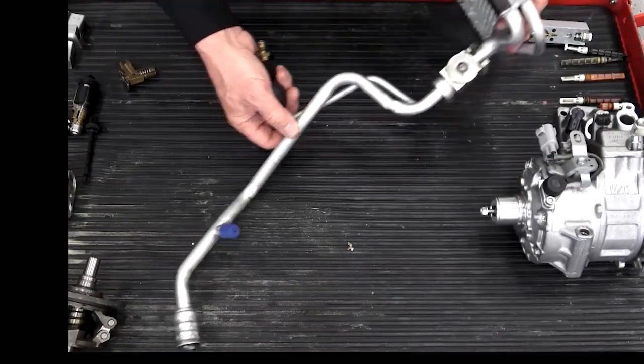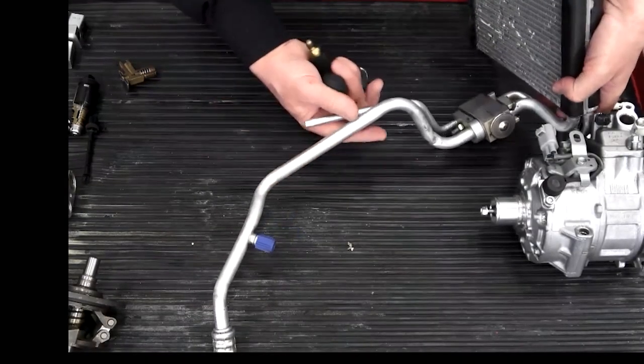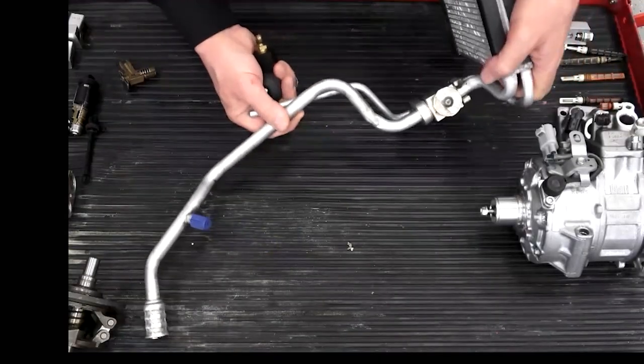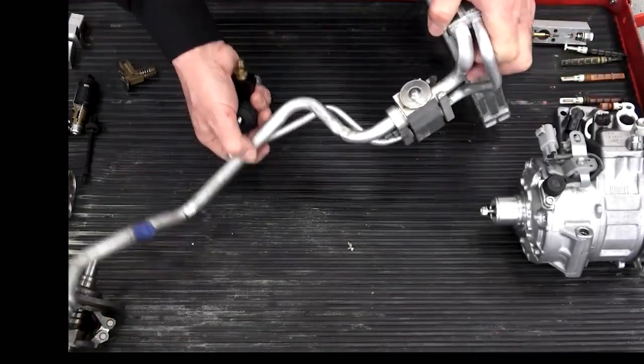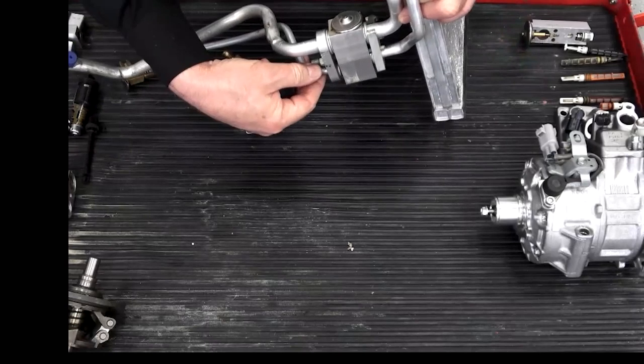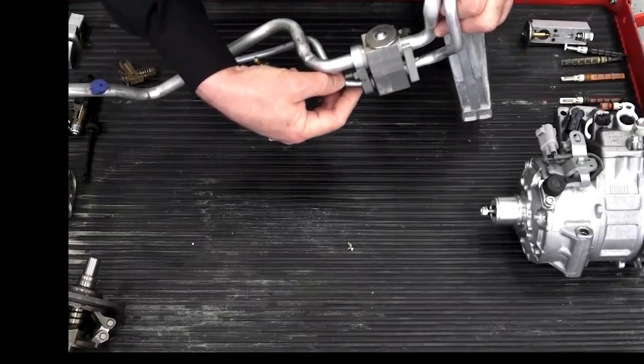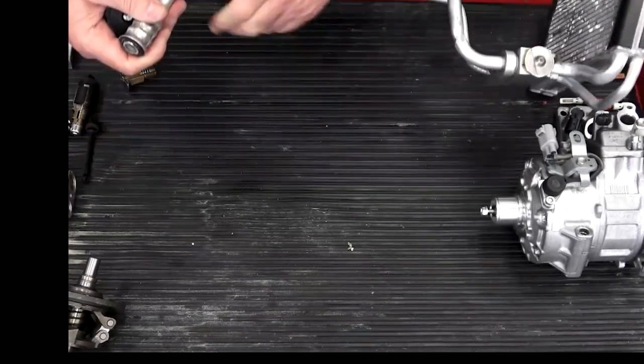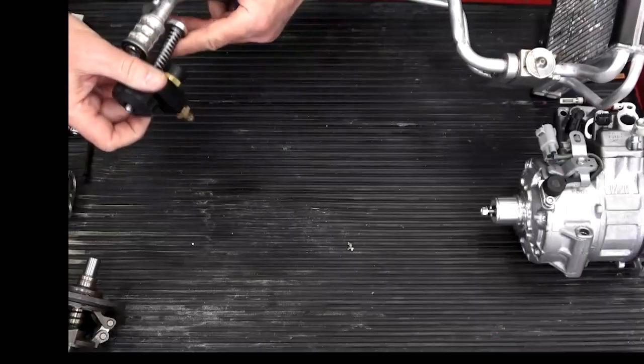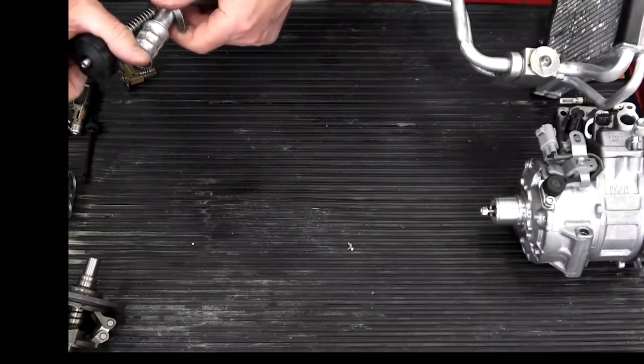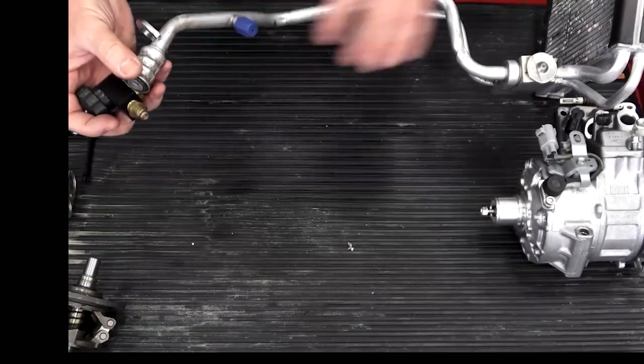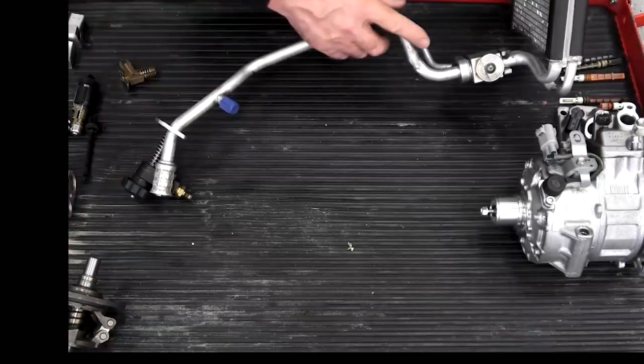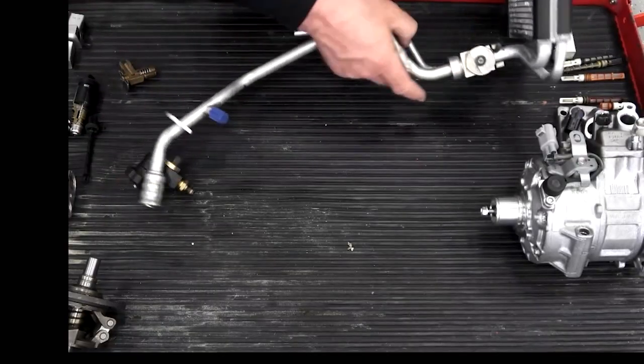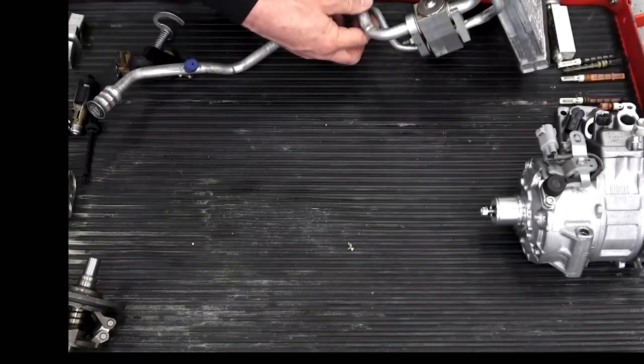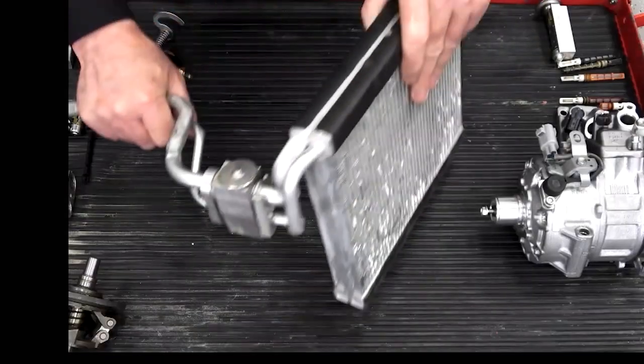So what I do is I take an old piece of liquid and suction line like you can see here, and then I take the TXV. You can't flush through a TXV valve, but I attach my flush tool here, like this, the tool that I just showed you, and so I can flush, reverse flow. I can flush through the evaporator and back out to the TXV. But as I said, you can't flush through a TXV.